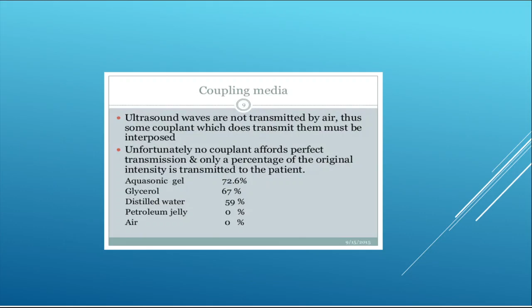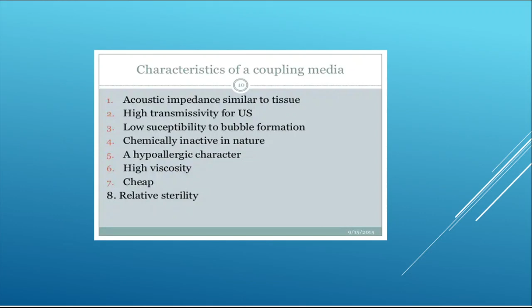Now the characteristics of the coupling media are that it should have acoustic impedance similar to tissue, high transmissivity for the US, and low susceptibility to bubble formation. If there is bubble formation, it can be harmful for the tissue. It should be chemically inactive in nature, hypoallergenic, of high viscosity, cheap, and relatively sterile for the tissue.